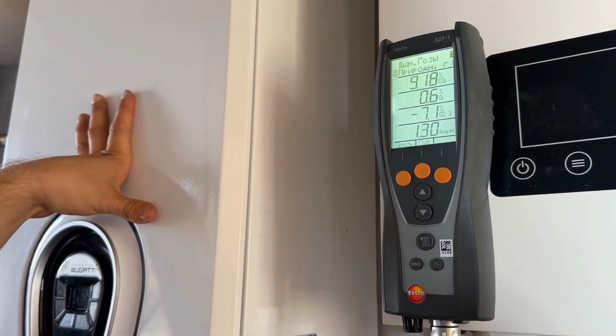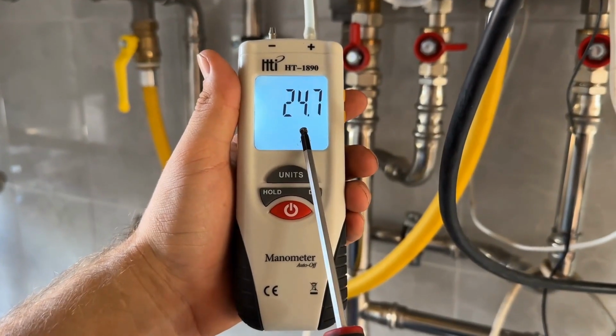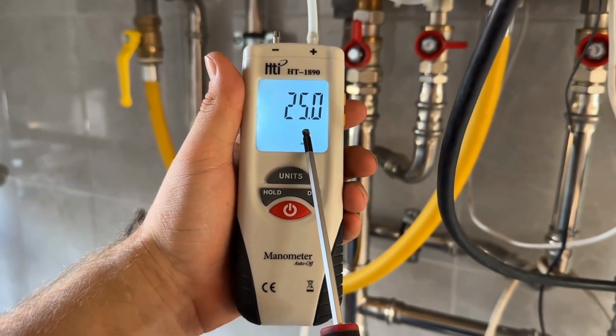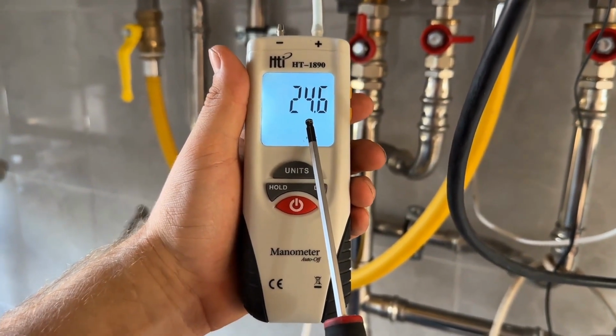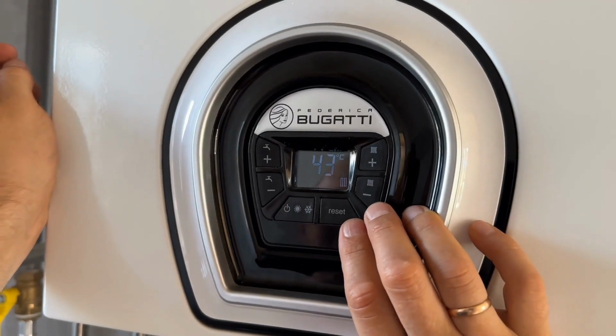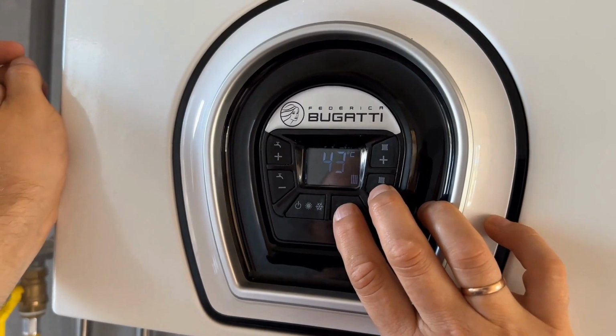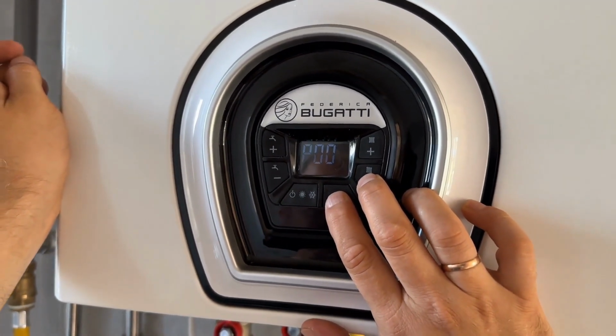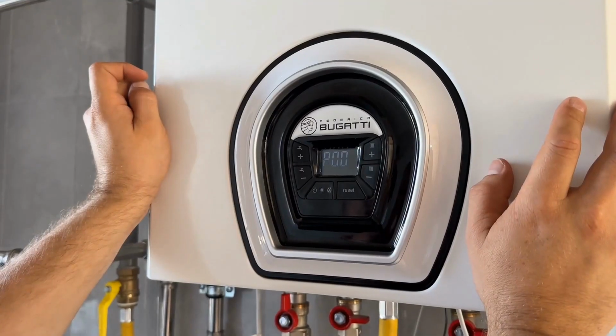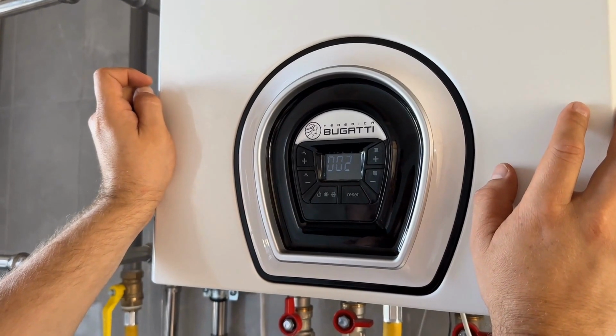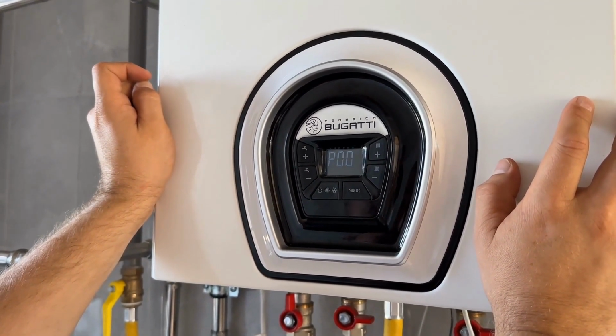We stop the measurement. Be sure to check the gas pressure dynamically. It should not be less than 13 millibars. After checking the composition of the exhaust gases, we enter the service menu by simultaneously pressing the reset and heating minus buttons. We check and modify the service settings if necessary. You can find more information about the service settings in the video.